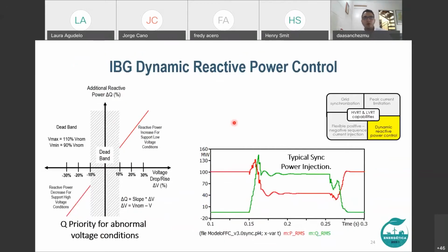Okay, let's go to the fourth. There are regulation requirements, and due to this, dynamic reactive power control is implemented. This control block determines the reactive power compensation under abnormal voltage conditions, establishing that for voltage perturbations the IBG works with priority. So when the PCC voltage is out of this dead band, the IBG works with priority. For undervoltage conditions, at this point, the IBG will inject more reactive power, and for overvoltage conditions, the IBG will consume reactive power. The compensation depends on the drop or rise of the PCC voltage, and is defined by a linear slope.